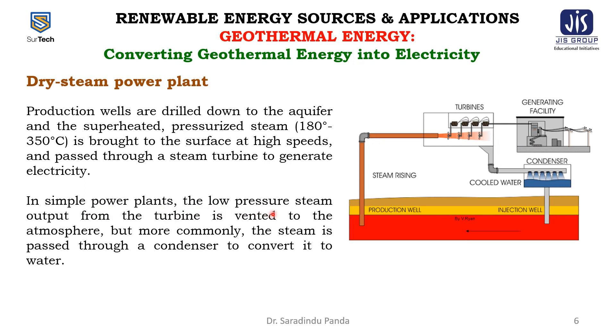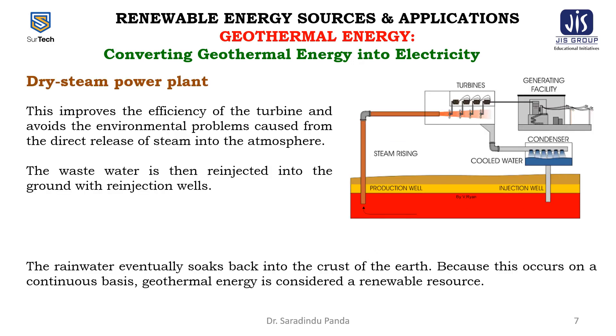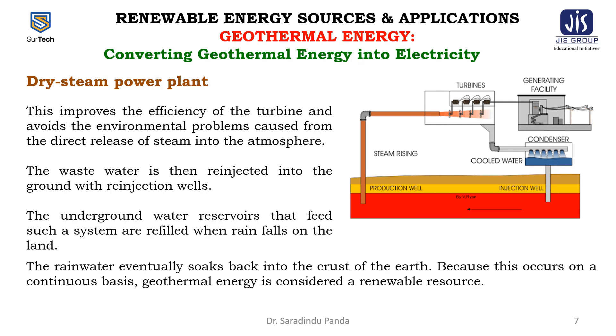In simple power plants, the low-pressure steam output from the turbine is vented to the atmosphere, but more commonly the steam is passed through a condenser to convert it to water. This improves turbine efficiency and avoids environmental problems caused by the direct release of steam into the atmosphere. The condensed water is then re-injected into the ground via an injection well. The underground water reservoirs feeding such a system are refilled when rain falls and soaks back into the earth's crust, which is why geothermal energy is considered a renewable resource.